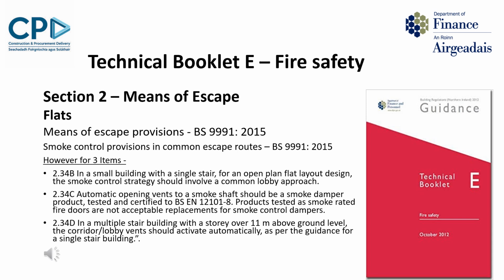With regard to smoke control provisions in the common escape routes of flats, TBE also now makes reference to BS 9991 2015. However, we did think the 2015 version was not in line with more recent guidance from the Smoke Control Association contained in Guidance on Smoke Control to Common Escape Routes in Apartment Buildings, Flats and Maisonettes of July 2020 publication.